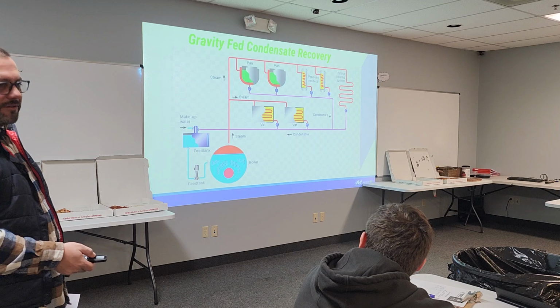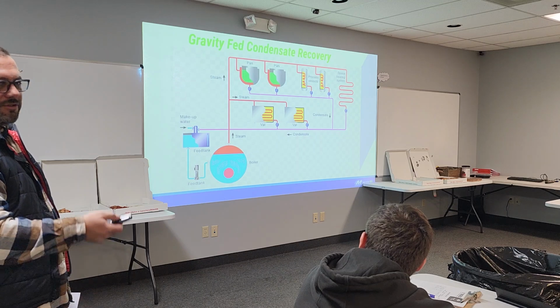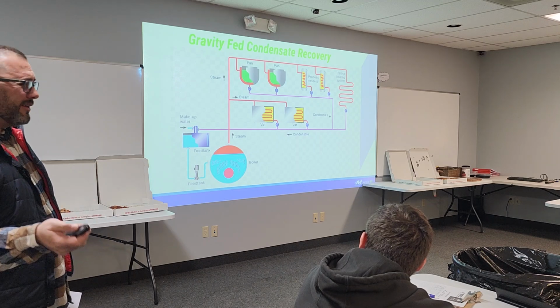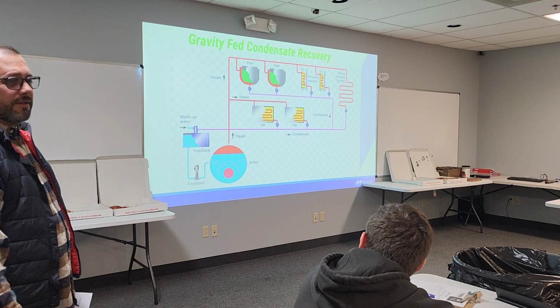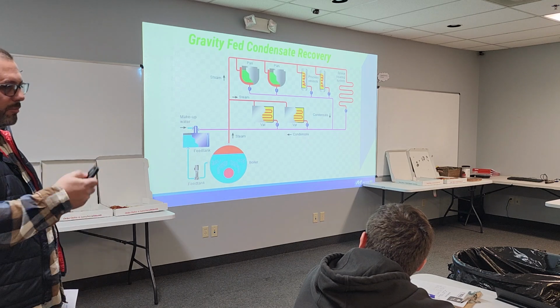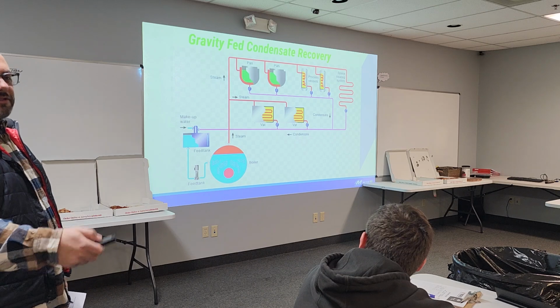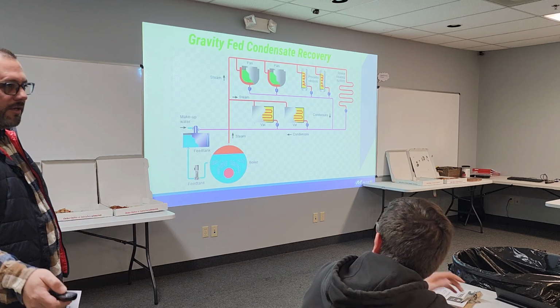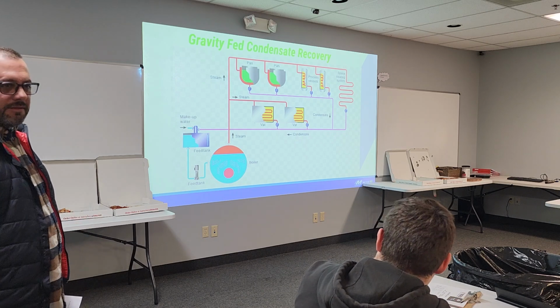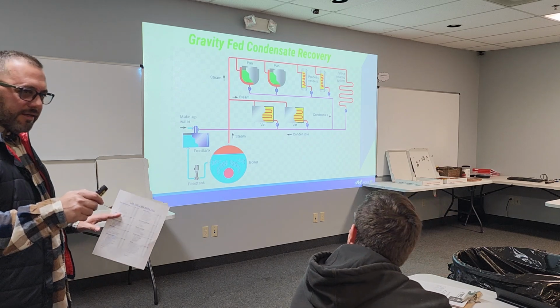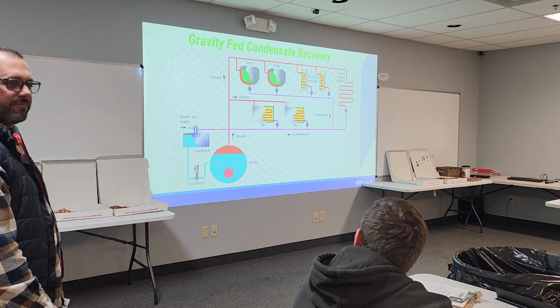Well, this time of year, it's frozen coils, to the tune of, I think, about $40,000 a coil. So we're in the process of redesigning the system, because they've done it years and years in a row, and they just keep throwing coils at it. The conditions have to be just right, but it only takes a few minutes.